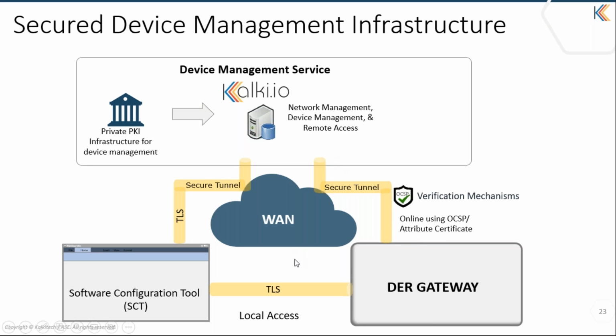Role-based access control is validated through two configurable modes. You can either select an online mode using OCSP, or go for attribute certificate-based mode, which is primarily offline, where an attribute certificate is issued to each user for each device, as per IEC 62351-8, the role-based access control standard.